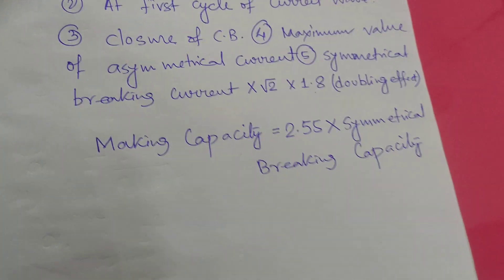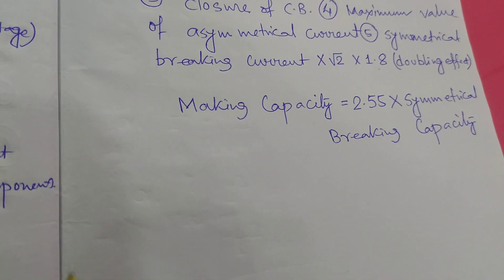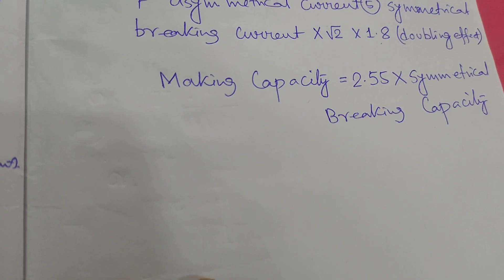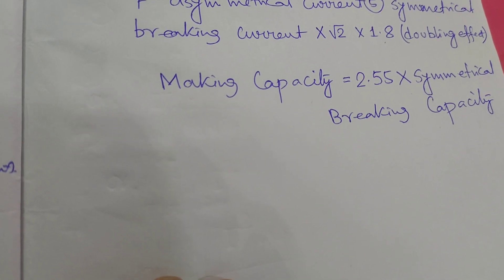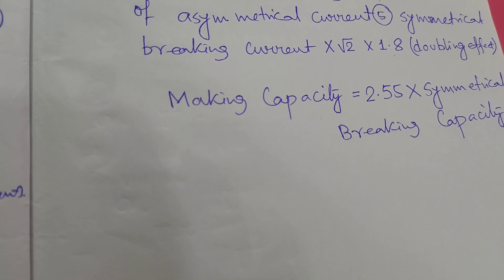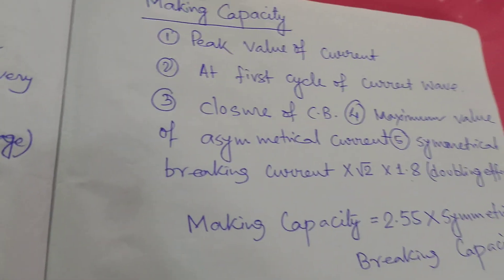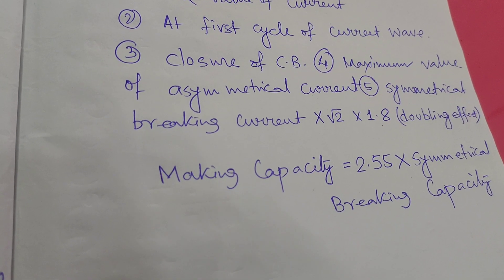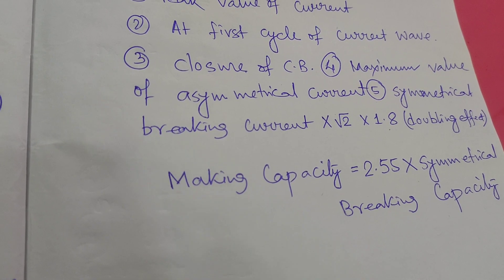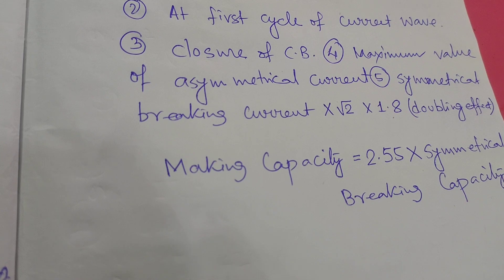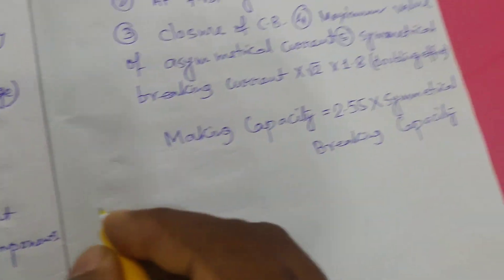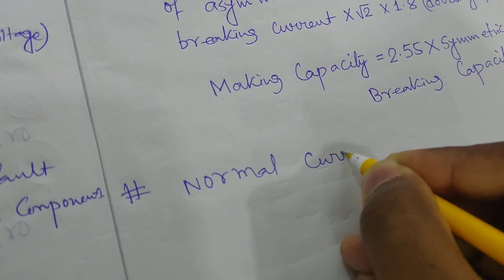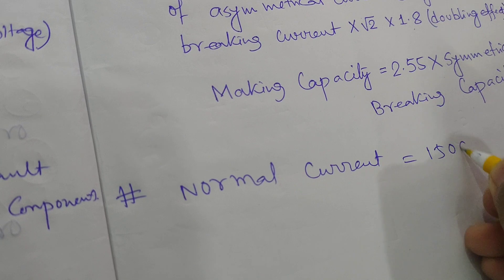For better understanding, let's do a problem related to breaking capacity and making capacity. A Circuit Breaker is rated as 1500 ampere, 1000 MVA, 33 kV, 3-second, 3-phase oil circuit breaker. Find: the rated normal current, breaking capacity, rated symmetrical breaking current, rated making current, short time rating, and rated service voltage. Rated normal current = 1500 ampere.